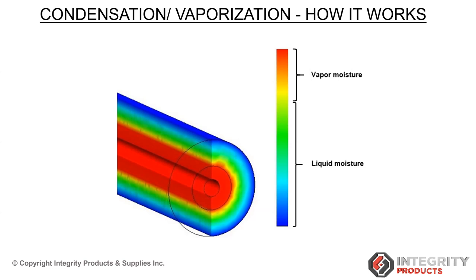We have another question here, Ahmad, which is asking, is there an acceptable level of moisture content for your insulation to have? The quick answer is no, it's zero at best. Exactly. But is there any range? We saw during the presentation that 5% moisture content increases the K value by 25%, which is significant. But is there anywhere in between that's deemed an acceptable level of moisture? Well, I would say there has to be a significant study on that. It has to be determined application to application, case to case, by the manufacturer and the specific insulation. Exactly. As I say, the quick answer is no. If you can keep your insulation completely dry, it's going to perform at its peak. But I think you're right as well, Matt, that there's a lack of data in the industry about that particular question.